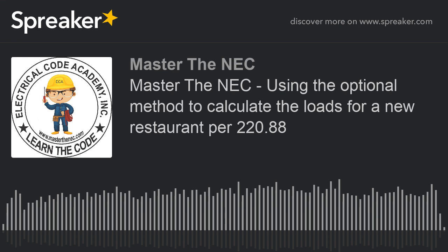Our example is going to be a total connected load of 450 kVA, so 450,000 VA. Once we establish our total connected load, which is either provided by the engineer or you literally added up every electric load in the building, you go to the first column and go down to the third row. It's between 326 and 800, because that's what our kVA is. We had 450, which falls right there in the middle.